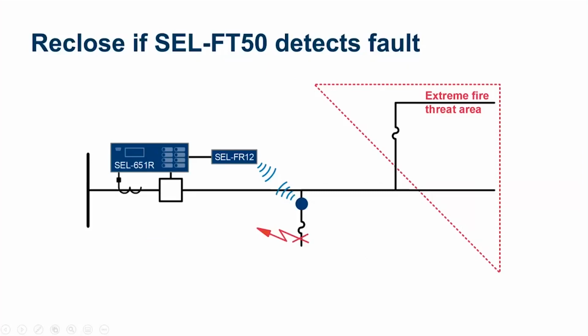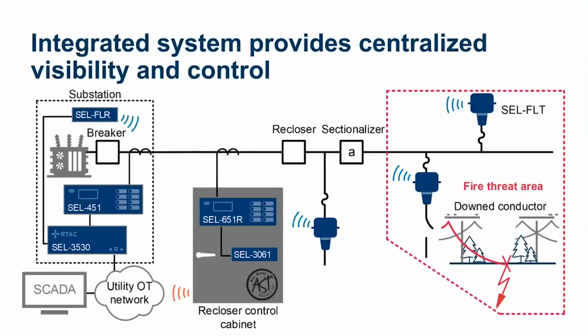So on distribution systems, you can install these FT50 and FR12 devices to allow reclosing in certain cases and block reclosing in others. So this is a handy little tool that can be used along with the 651R to make high impedance fault detection more reliable or to avoid wildfire hazards. So this is the integrated wildfire approach that you can take to minimize the hazards, as Anthony mentioned.